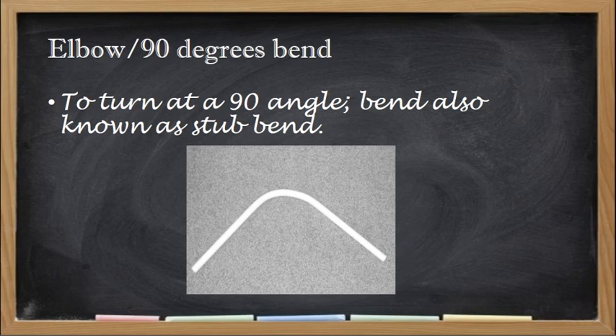It is used to turn at a 90-degree angle. The bend is also known as the stub bend because a 90-degree bend has two parts: the stub is the shorter part of the conduit, and the longer side is called the tail. The elbow or 90-degree bend is used to turn conduits at a 90-degree angle, especially when the bend is coming from the floor and we want the run to go up the wall.